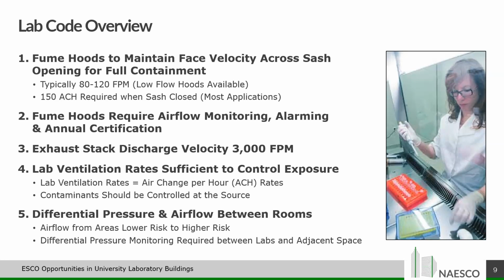You also need to certify your fume hoods on an annual basis, that they are operating within these face velocity requirements, and that there are no cross drafts in the room that could come in and create a hazardous environment. That is required of all lab fume hoods once a year, and a report is generated annually for each one at the universities, in most cases, that shows all the results of that testing.